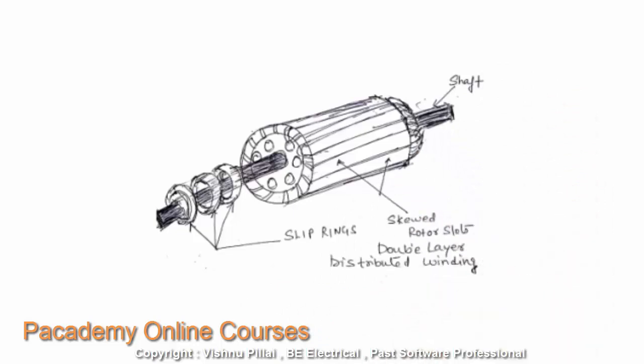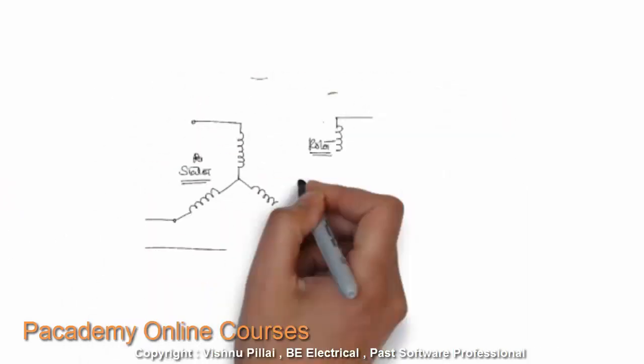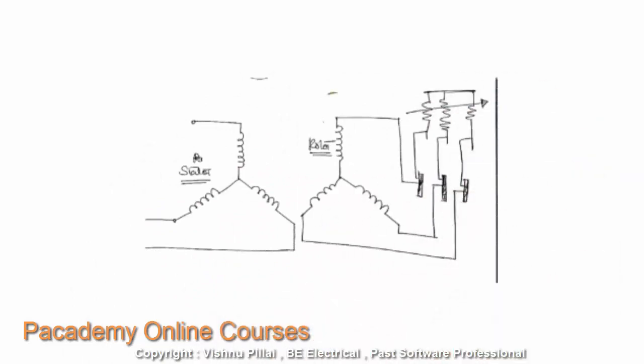One arrangement to avoid this is to use a wound rotor induction motor, which has double-layered windings as opposed to the rotor bar cage arrangement. The windings are connected in star internally for the three phases, and other leads are brought out and connected to three slip rings. These slip rings, via brushes, are connected to external resistance, allowing resistance to be added to the rotor circuit at the time of starting. This increases the rotor torque and also reduces the rotor current.